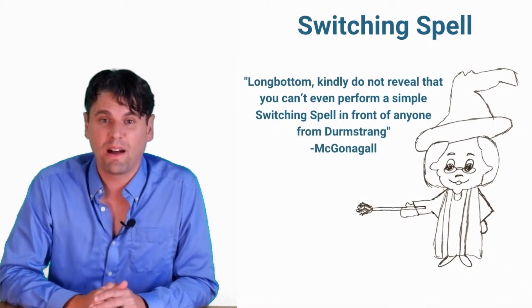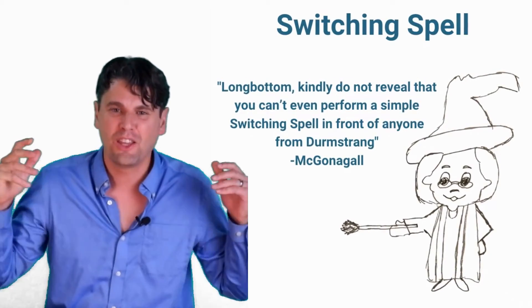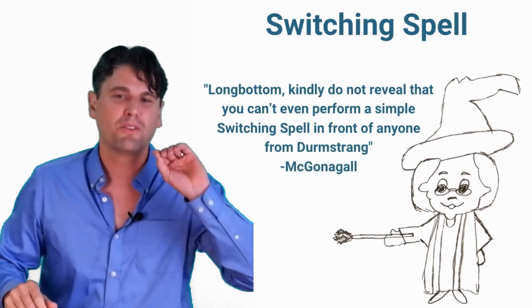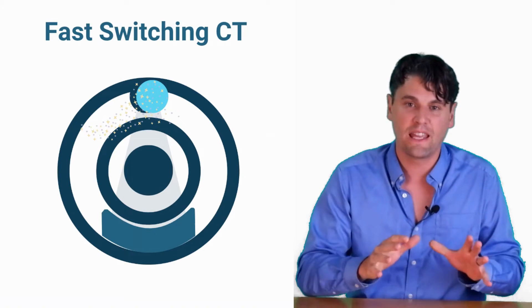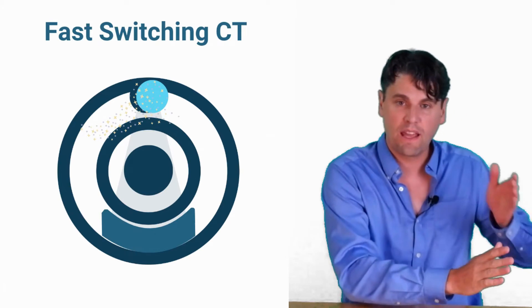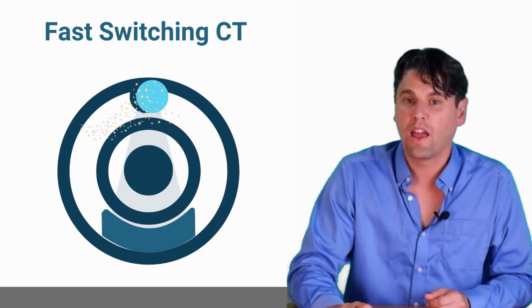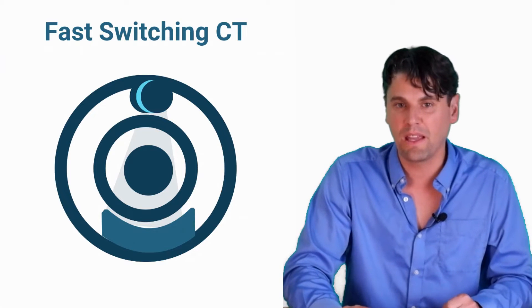The first approach is the switching spell. McGonagall called out Longbottom and said you probably can't even perform a switching spell. In terms of switching, we're talking about fast switching between those different KVPs. Changing the KVP will change the energy spectrum used. So if you could switch from view to view — high KVP, low KVP, high, low — you could use that information in order to reconstruct the dual energy information. This is how a true fast switching CT system works.